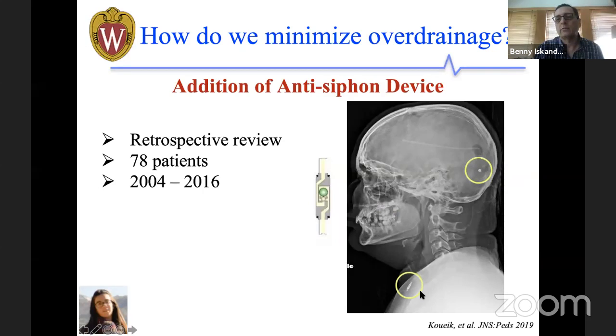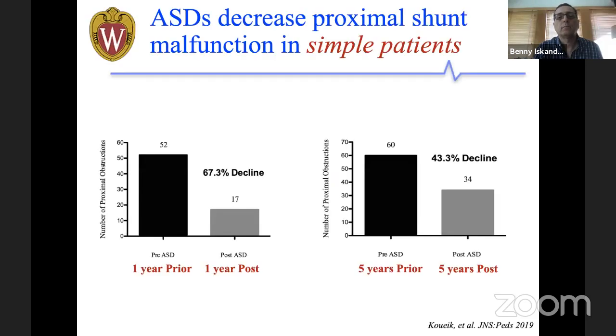So this is the primary valve, and this is the anti-siphon device that we're placing to decrease the flow from the shunt system. Now, of course, if your primary valve is in the coronal region, you can put the anti-siphon device in the occipital region. The idea is to separate it by at least 10 centimeters. And these are the data. In patients who've not had a lot of shunt revisions, we cut down on the shunt obstruction rate, or proximal shunt obstruction rate, by 70% in the first year and by 43% in year 5.